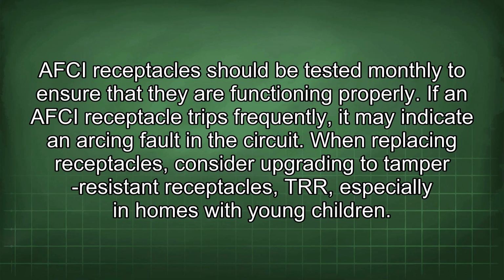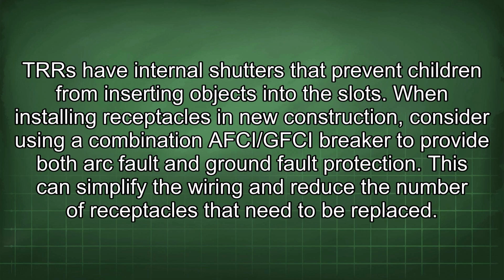When replacing receptacles, consider upgrading to tamper-resistant receptacles, TRR, especially in homes with young children. TRR have internal shutters that prevent children from inserting objects into the slots. When installing receptacles in new construction, consider using a combination AFCI/GFCI breaker to provide both arc fault and ground fault protection. This can simplify the wiring and reduce the number of receptacles that need to be replaced.